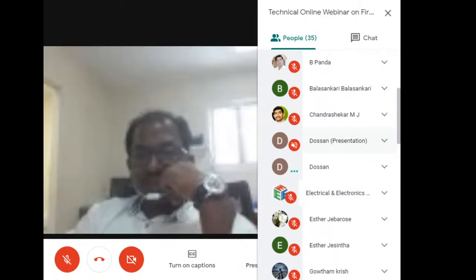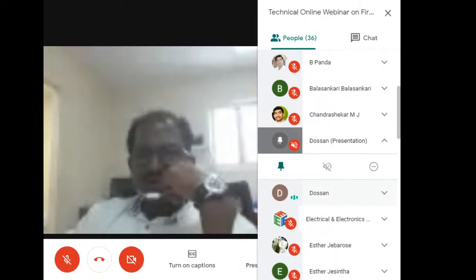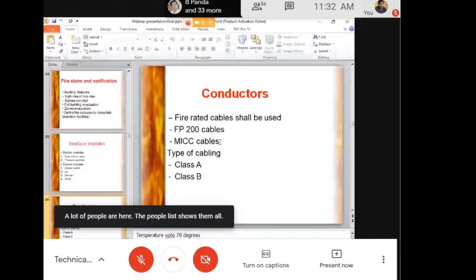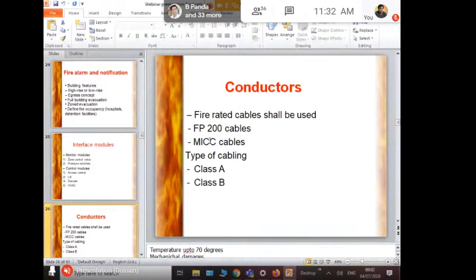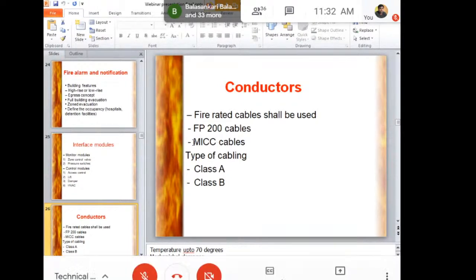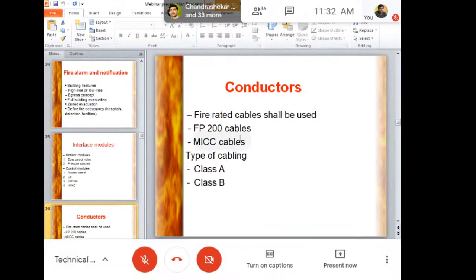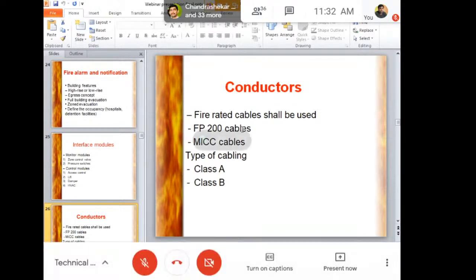So we have to go for FP200 cables, which is fireproof 200 cables. So it depends on the project again. And we can use MICC cables also. MICC is mineral insulated copper conductors. So these cables are preferably used for fire alarm systems.